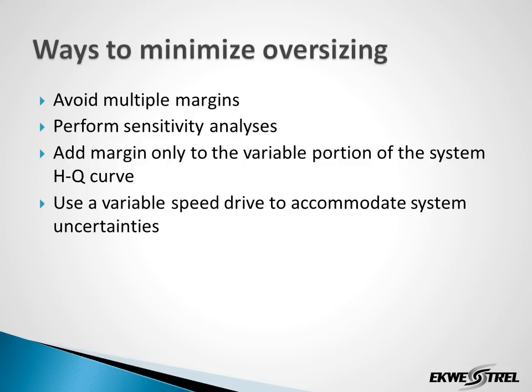How do we minimize oversizing of a pump? Be cognizant of margins on top of margins. For instance, if margins are already added to the friction factors, then is it necessary to then add margin to the pump? Where uncertainties exist, vary parameters and determine the range of outcomes. Most often, the static portion of the system head is well-established. Separate out the static portion and apply margin only to the variable portion of head. Finally, use a variable speed drive to accommodate system uncertainties.